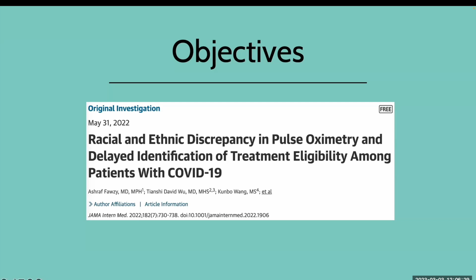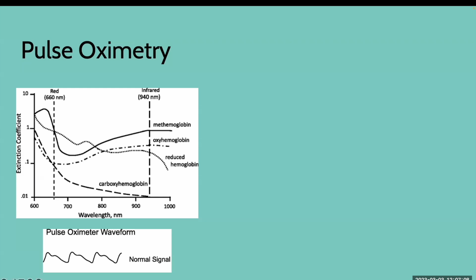This was designed to measure oxygen saturation by illuminating the skin and measuring changes in light absorption of oxygenated and deoxygenated blood using two wavelengths. The ratio of absorbance at these wavelengths, calibrated against measurements of arterial saturation, establishes the oximeter's approximation of arterial saturation. The waveform, available on many pulse oximeters, assists clinicians in distinguishing an artifact from the true signal. The concept was applied to create multiple sites of light transmission, reflectance, and detection, suitable for the finger, toe, earlobe, and forehead. But in the early literature, certain limitations were clearly identified that could impact the detected light.